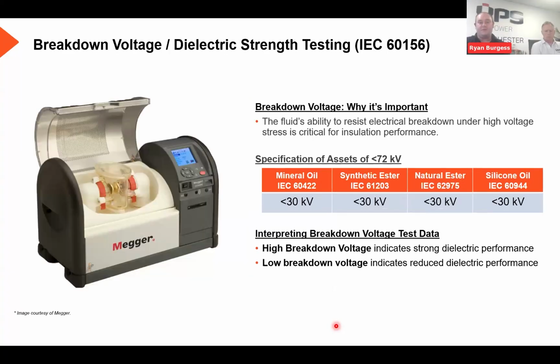So from the fluid quality tests, we'll look at the final test, and that's breakdown voltage. Breakdown voltage can also be known as dielectric strength, depending on who you speak to. It's the same thing, just a different term. Breakdown voltage is the measurement of the fluid's ability to withstand an electrical stress without it failing. So what causes that to fail? It's usually particulates in the fluid, but it's also linked to the moisture as well. And it's an early warning sign of the degradation of the fluid as well as the water and the acidity.